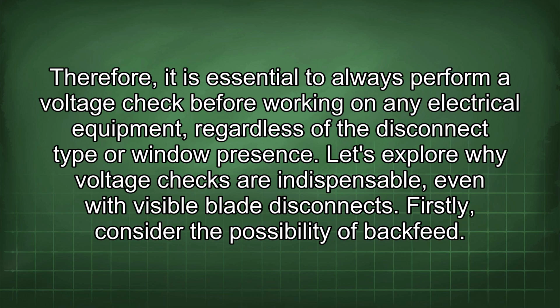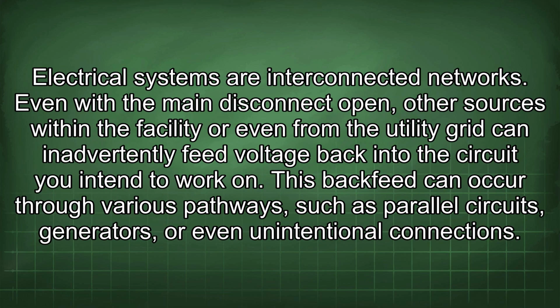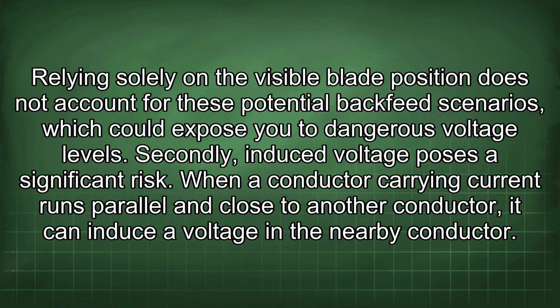Firstly, consider the possibility of backfeed. Electrical systems are interconnected networks. Even with the main disconnect open, other sources within the facility or even from the utility grid can inadvertently feed voltage back into the circuit you intend to work on. This backfeed can occur through various pathways, such as parallel circuits, generators, or even unintentional connections. Relying solely on the visible blade position does not account for these potential backfeed scenarios, which could expose you to dangerous voltage levels. Secondly, induced voltage poses a significant risk.